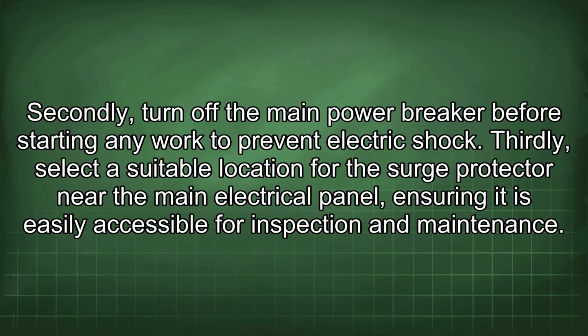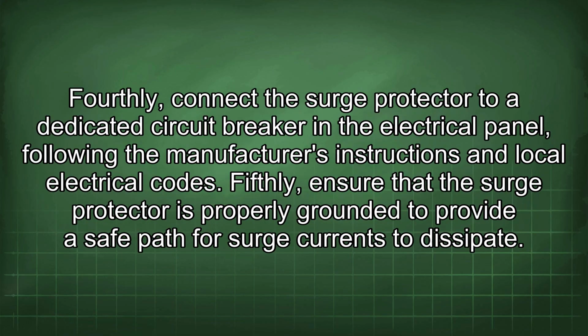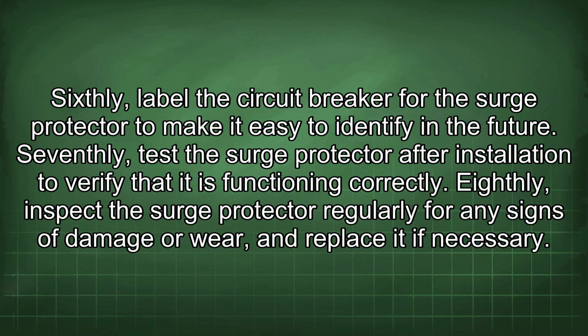Thirdly, select a suitable location for the surge protector near the main electrical panel, ensuring it is easily accessible for inspection and maintenance. Fourthly, connect the surge protector to a dedicated circuit breaker in the electrical panel following the manufacturer's instructions and local electrical codes. Fifthly, ensure that the surge protector is properly grounded to provide a safe path for surge currents to dissipate. Sixthly, label the circuit breaker for the surge protector to make it easy to identify in the future. Seventhly, test the surge protector after installation to verify that it is functioning correctly.